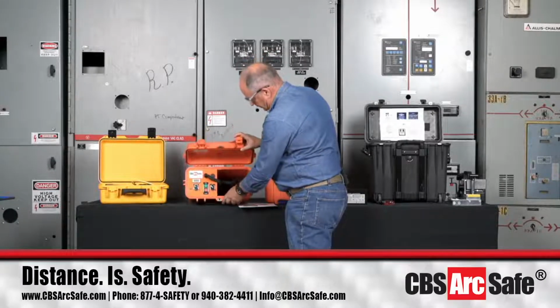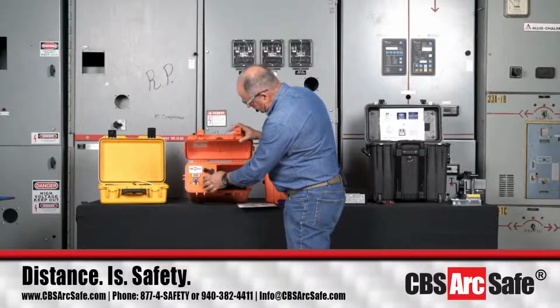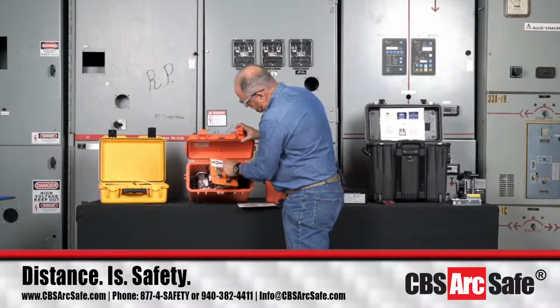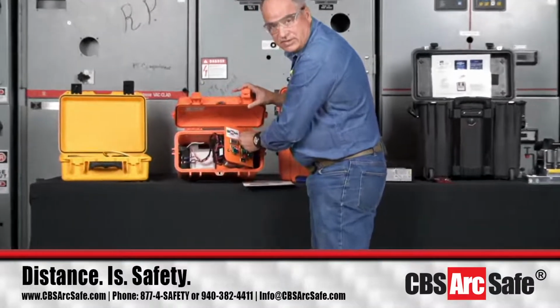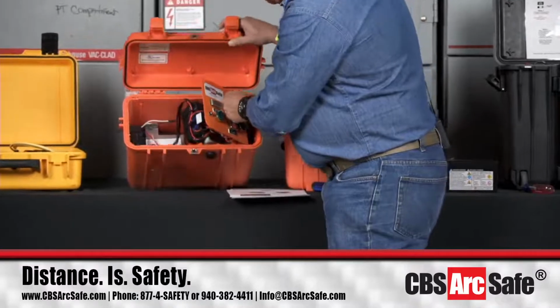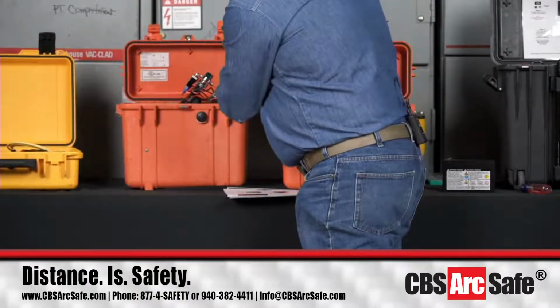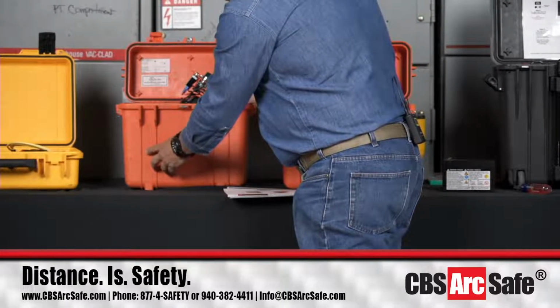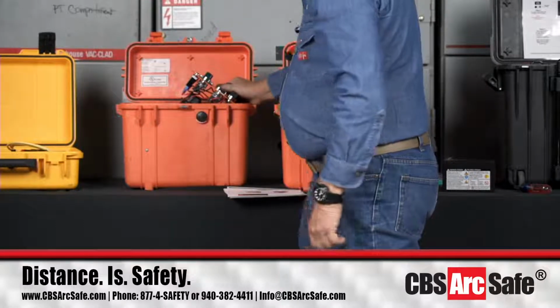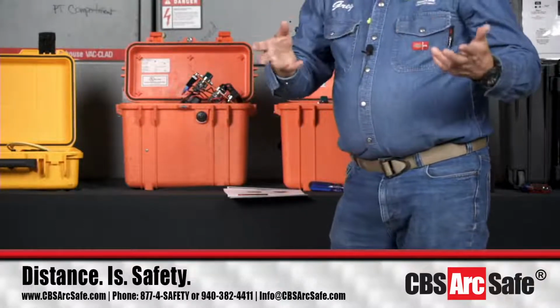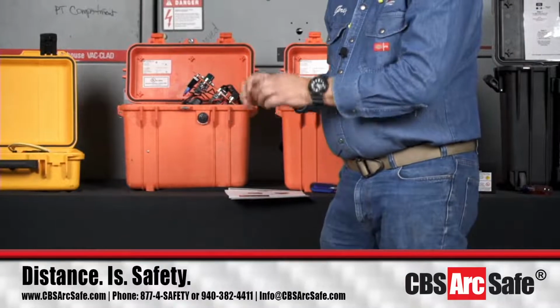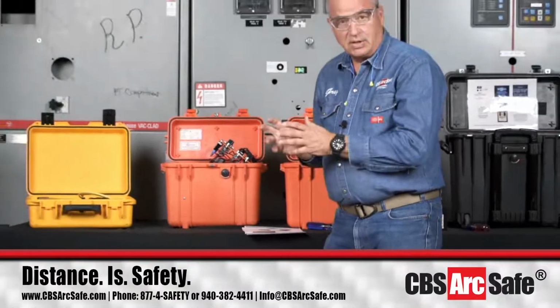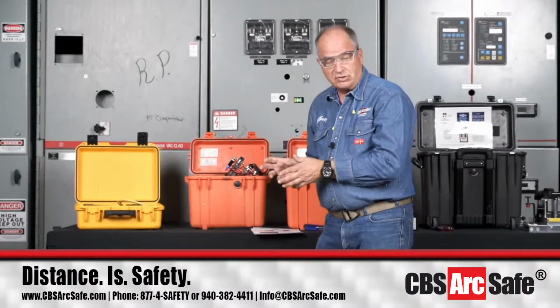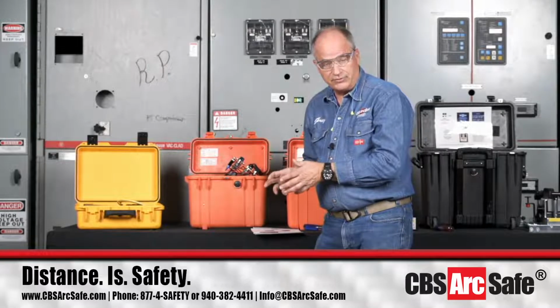The unit comes like this, and what we do is pull this off, and you can see the batteries down inside. There's a battery strap screw on the front and one more on the back. So once a year you're going to expose this, unplug the unit, and check the batteries to make sure each one's holding 12 volts.